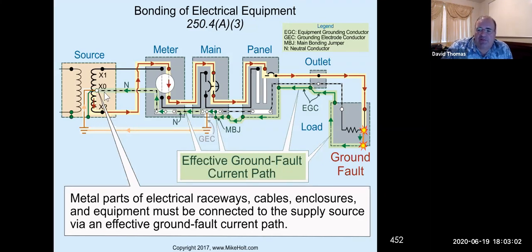Okay. Also notice that we have this green path, but we also have the ground rods here. We have a ground rod at the transformer. We have a ground rod at the main service. Some of the electrons do flow back through earth from one rod to the other rod. Also, many studies have shown about 5% will flow back through that pathway, about 5% during these fault conditions. Okay, so in here, typically 5% of the current will flow down this way back to the source, but 95% will flow on the equipment ground.